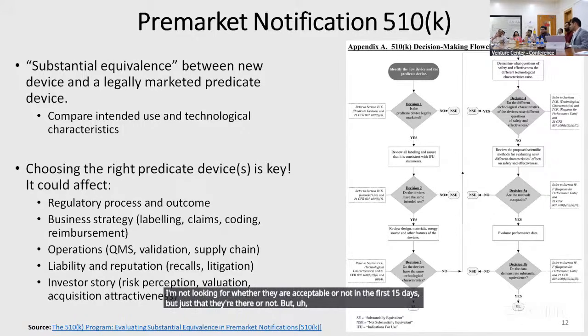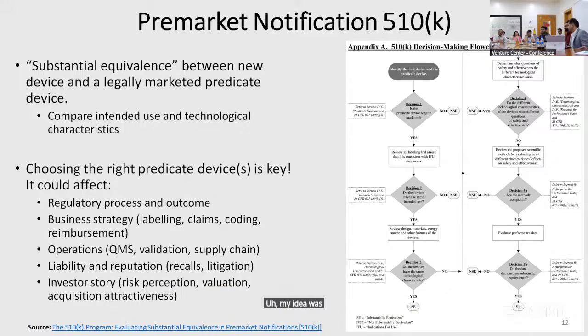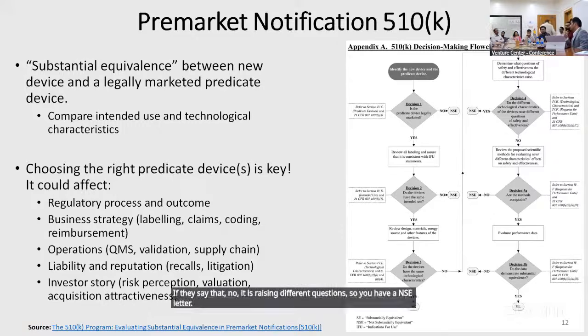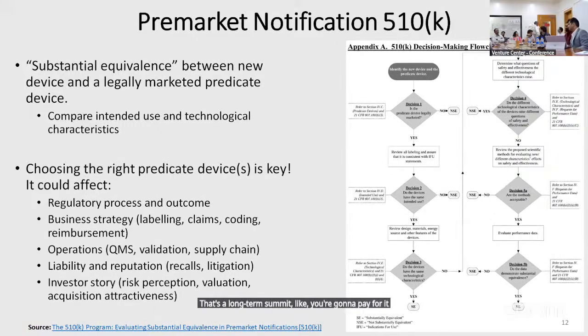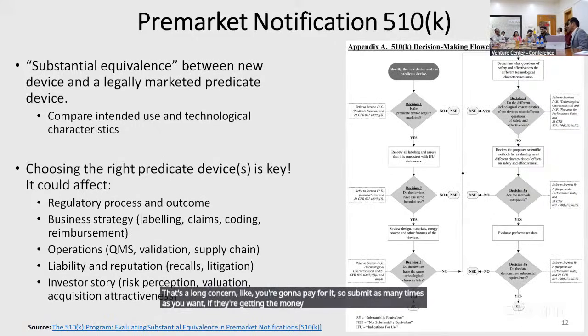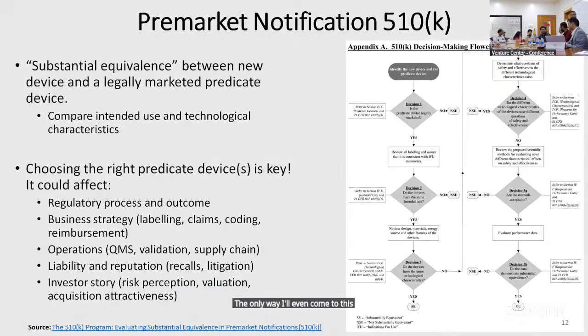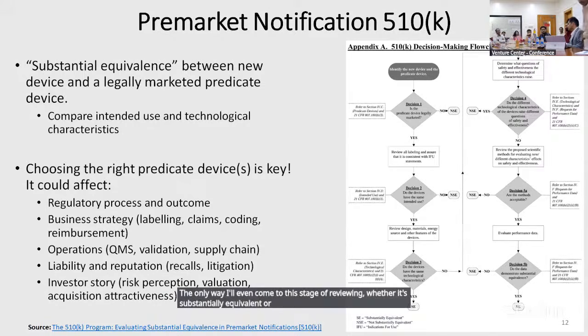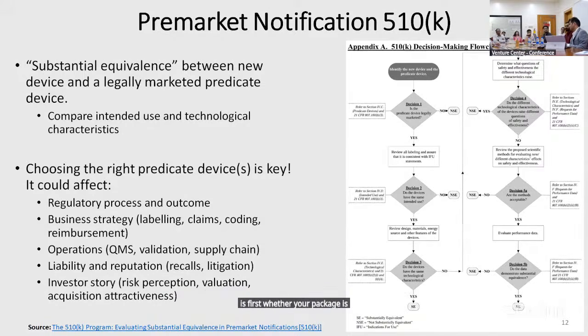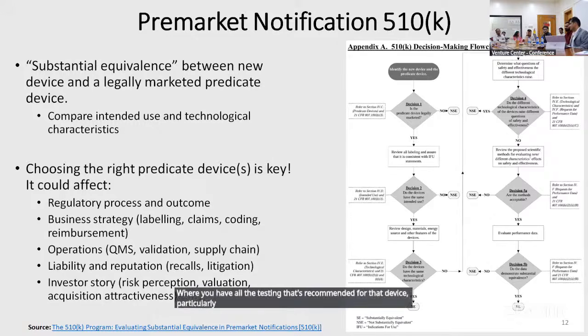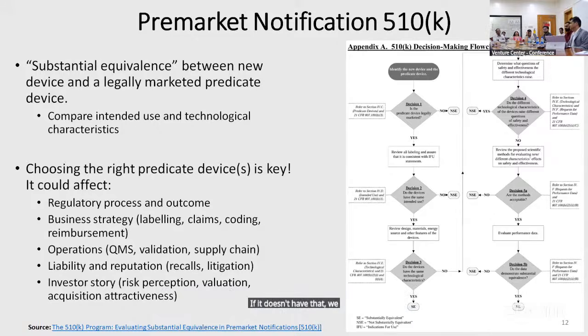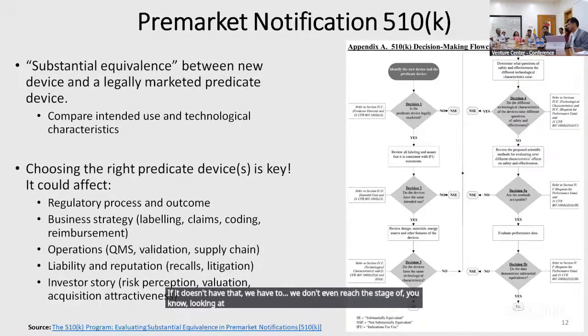But my idea was they don't give you a chance to submit the test reports. If they say no, it is raising different questions, so you have an NSE letter. That's not true. You can submit as many times as you want, since you're going to pay for it, and they're getting money out of it, right? So they don't have any problem with that. But the only way I'll even come to the stage of reviewing whether it's substantially equivalent or not is if your package is complete. Do you have all the testing that's recommended for that particular device or not? If it doesn't have that, we don't even reach the stage of looking at substantial equivalence.